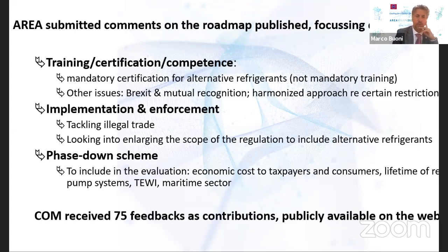For phase down, we should include not only stationary systems like air conditioning, but also maritime ships. We should also include energy efficiency, not only the phase down related to the global impact of the refrigerant itself, but how energy efficiency of systems is affected by changing refrigerants. If we change the refrigerant and efficiency goes down, we should not change it. We should look at energy efficiency globally, like the TEWI, the total equivalent warming impact of the system.